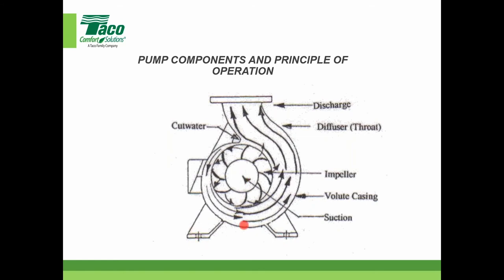Feet, right? Makes sense there. There's little holes here. Most the volute, casing, called the wet end, the volute, the casing, that's the big metal piece that everything's contained within, that sits on the base or in the piping system or whatever. In our industry, it's mostly cast iron for the most part. I forgot the exact grade, but nonetheless, it's just a pretty straightforward cast iron piece. And most of us pump manufacturers, anytime I say us, I'm referring to Taco in our competition. So pump manufacturers, us, I apologize. I just rattled it off so quick.